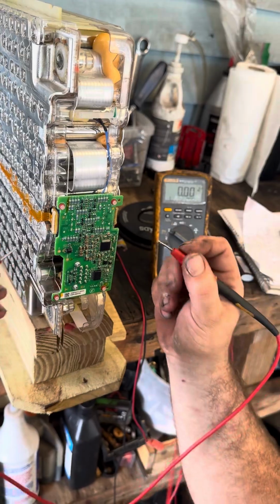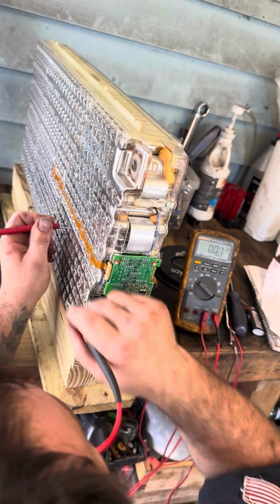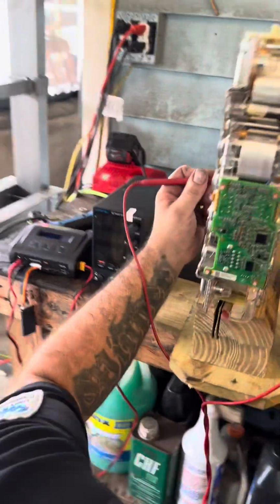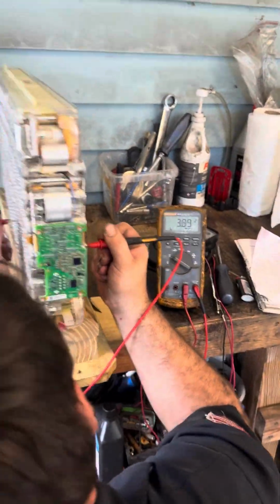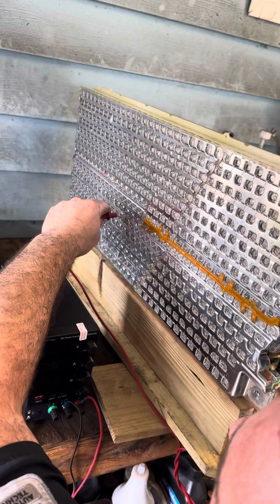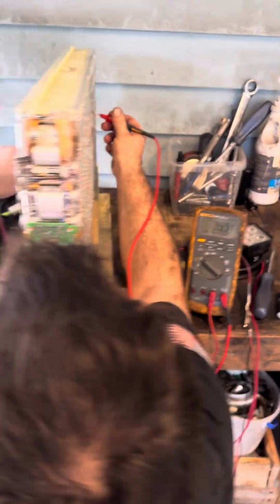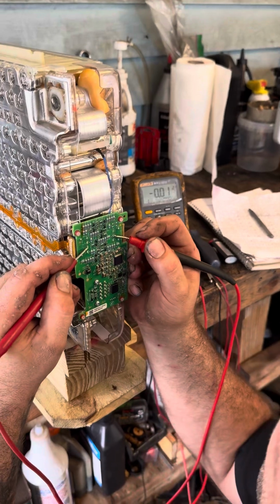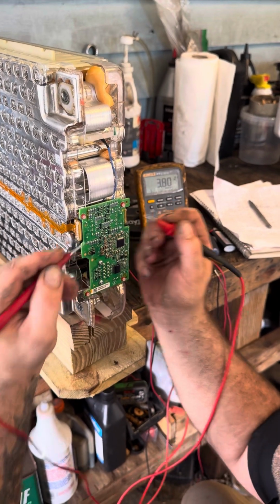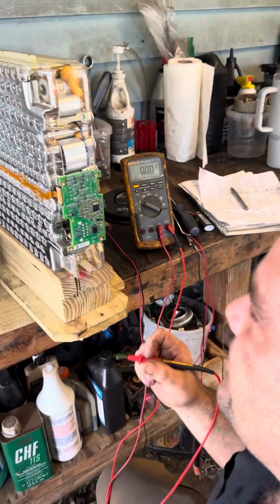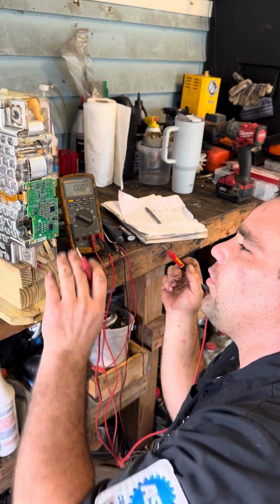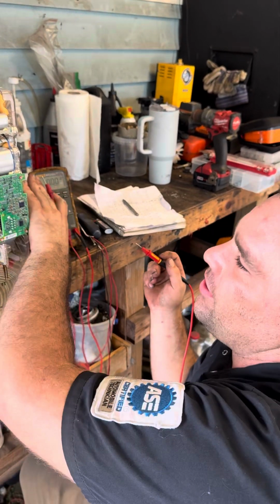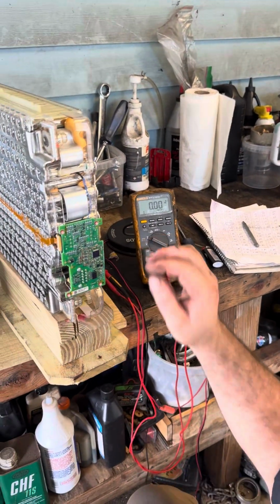So now that cell 3, the BMS, is reading 3.80. But if we were to check cell voltages from the module itself, and this is how it works. So this is going to be cell 1 at 3.89, and then you go to cell 2, 3.89, cell 3, 3.99. So it's reading way off from where it actually is. This BMS board is bad. There's some kind of resistance either in the board, more than likely in the board. So it's overcharging this one cell. So essentially this BMS board is bad.